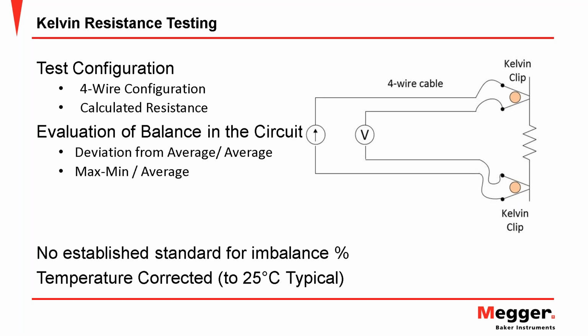So we do this precision balance measurement with the aid of what we call a 4-wire Kelvin bridge circuit. And I'm showing you the circuit here. Basically, we use a constant current source to pass current from the attached point in the motor circuit, typically at the terminals of the motor, or maybe even from the switchgear, and then measure directly across 1 phase of that particular motor winding. And so we pass the current flow across that circuit and then measure the voltage drop across the circuit at the point of contact. And that eliminates any resistance of the lines that could contribute to that reading, and it makes it very accurate. And it's very important, of course, that we make good connection on either side of that clip to make sure we get a good reading.